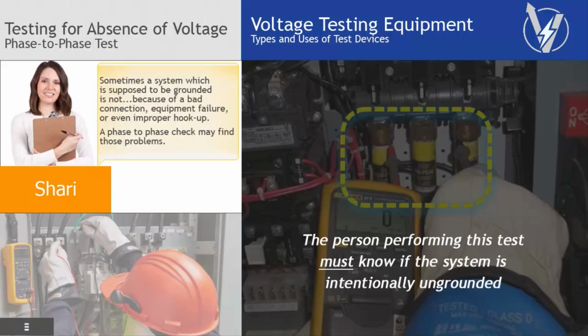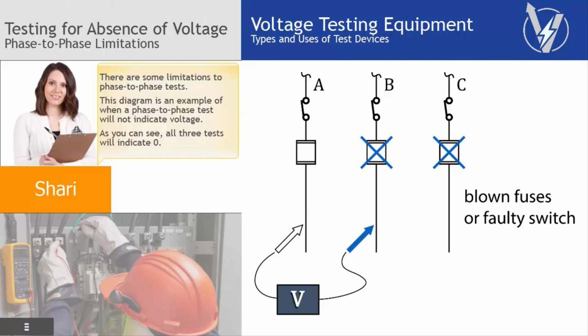Sometimes a system which is supposed to be grounded is not because of a bad connection, equipment failure, or even improper hookup. A phase-to-phase check may find those problems. There are some limitations to phase-to-phase tests. This diagram is an example of when a phase-to-phase test will not indicate voltage. As you can see, all three tests will indicate 0.